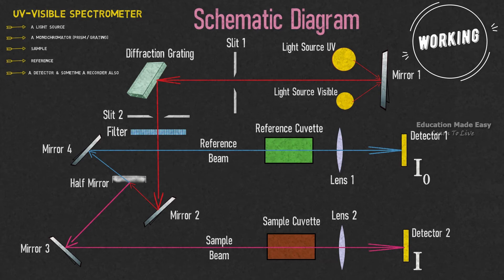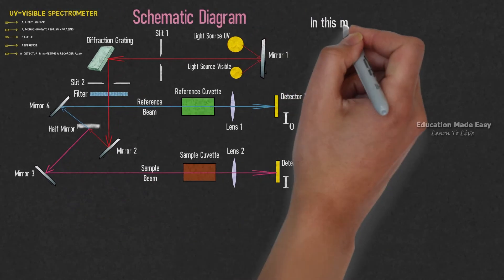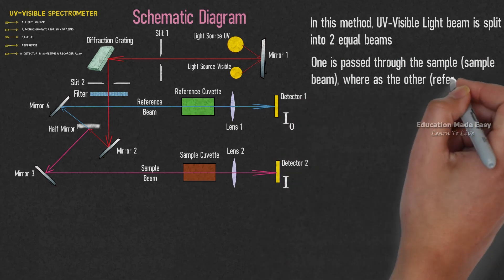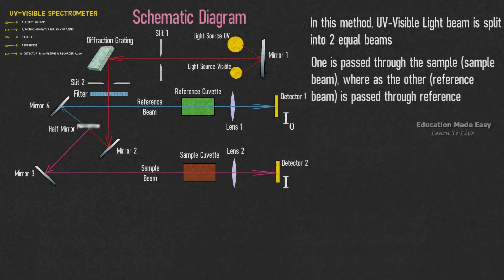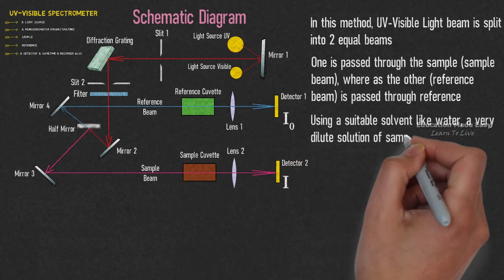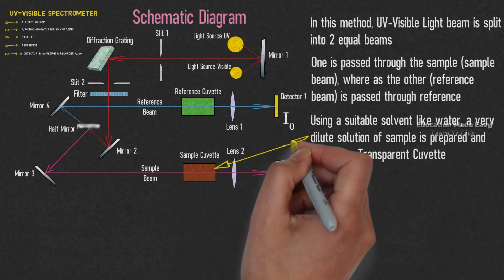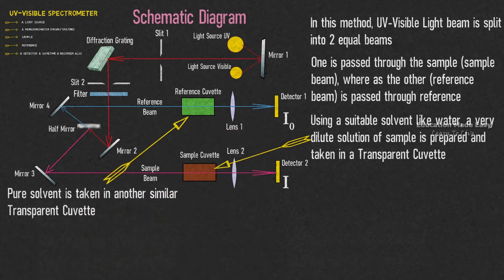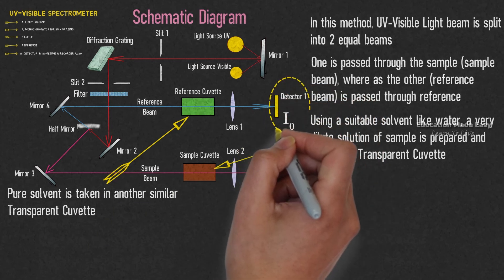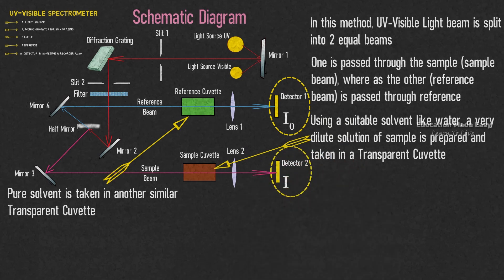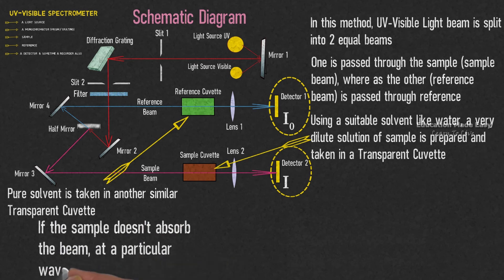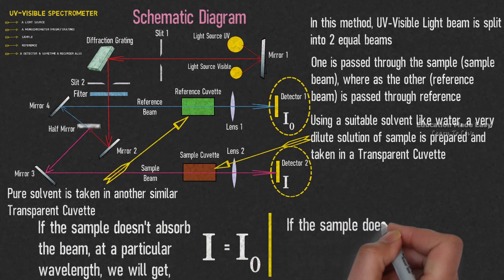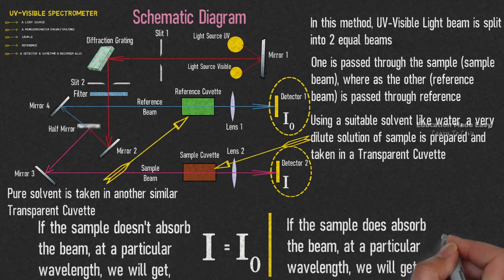The intensity of the reference beam and sample beam is compared to understand the sample. In this method, UV visible light is split into two equal beams — one is passed through the sample, called the sample beam, whereas the other, the reference beam, is passed through the reference cuvette. Using a suitable solvent like water, a very dilute solution of sample is prepared and taken in a transparent cuvette, represented in the figure as a brown box. Pure solvent is taken in another similar transparent cuvette, represented as a green box. The intensity of light at detector 1 (I0) and intensity of light at detector 2 (I) is compared. If the sample doesn't absorb the beam at a particular wavelength, we get I equal to I0. If the sample does absorb the beam at a particular wavelength, we get I less than I0.